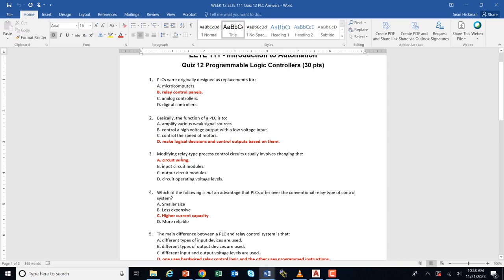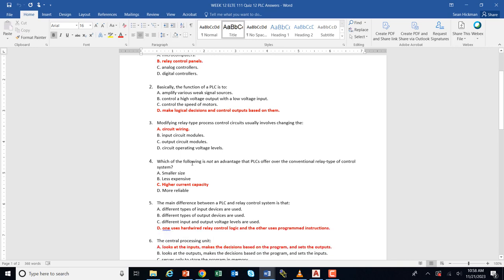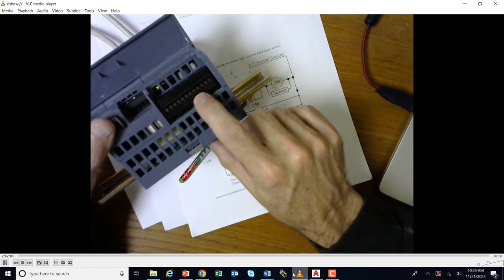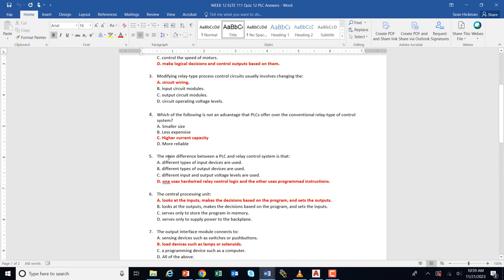Modifying relay-type process control circuits usually involves changing the circuit wiring — you've got to get your screwdriver and wire cutters out to make changes. PLCs are smaller, less expensive, and more reliable. However, PLCs do not handle really large current — the screw terminals are very small, so you can't run really thick wire. If you need really large loads, the PLC isn't designed for high current capacity, so you have to use an interposing relay. The main difference between a PLC and a relay control system is that one uses hardwired relay control logic and the other uses programmed ladder logic — to change it, you just change the program.